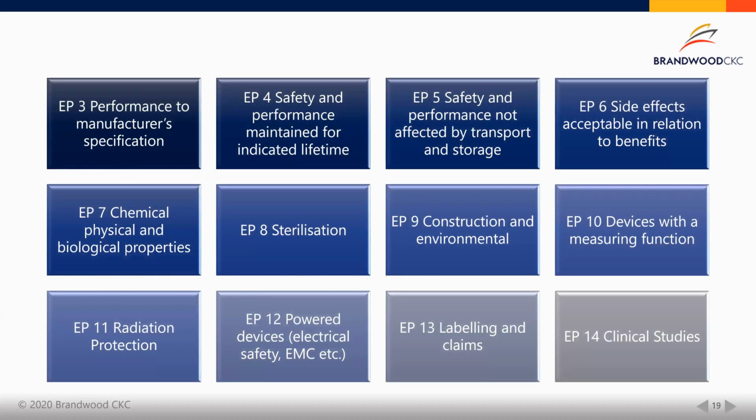These are a few more essential principles. So you can see that most of it makes sense. I mean, you've got sterilization, lifetime stuff, the properties, all of these are requirements that all devices must comply with. If it's something that doesn't apply to your device, that's fine. You can just say it doesn't apply. For example, if your device doesn't have a measuring function, then EP10 wouldn't apply to yours. EP12 is the one I'm going to point out, because that's for your powered devices. So that's an important EP for you guys.